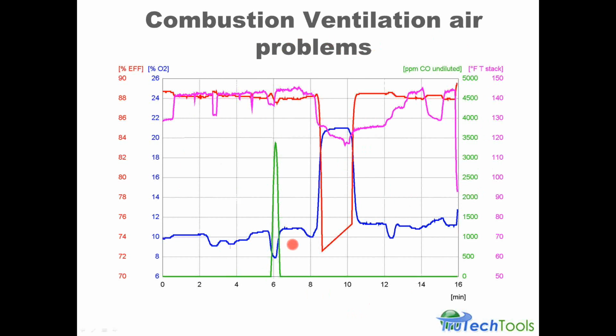Combustion air, this was a ventilation issue, but in this case, the point we want to drive home is you need to have a digital analyzer with a multi-line display telling you this important information, because it's changing all the time and everything is interrelated.